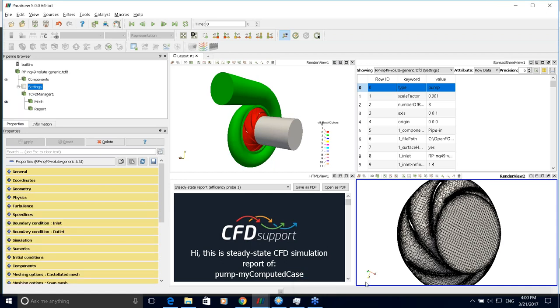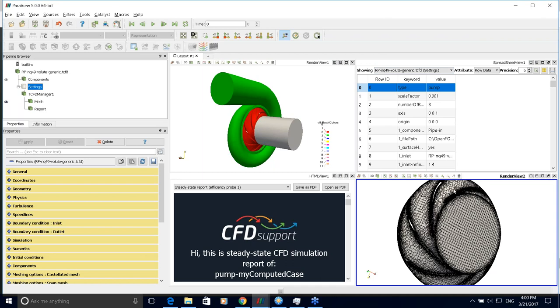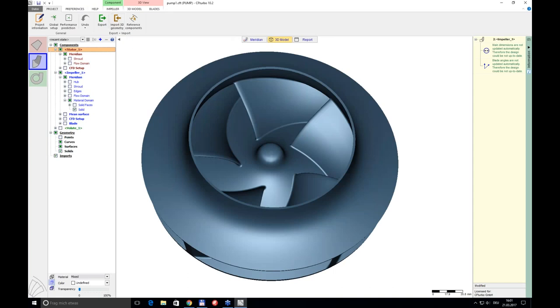Question from Dustin: where do you obtain your predictive values, for example B2 over D2 versus specific speed? CF Turbo is based on turbomachinery design theory. We solve balance equations, but for a good initial design you also need empirical relations and similarity numbers, taken from all publicly available sources — textbooks, papers, and so on. References are always shown within the software. If your experience differs, you can add and incorporate your own curves at any time and they stay private.